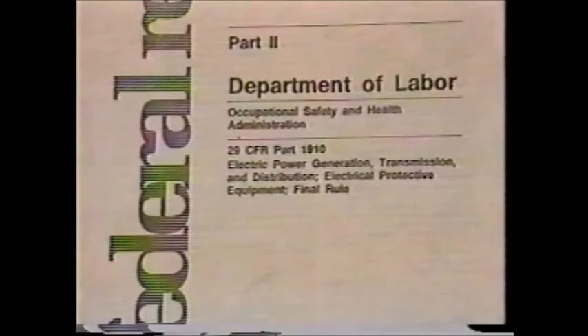OSHA doesn't specify a value of leakage current. They do reference an IEEE standard which covers various methods of testing tools. The section in IEEE relating to full scale high voltage testing also doesn't give an accept reject value. Rather it states that the reading should be steady or decreasing. Obviously both standards require by inference that the tool may not flash over.